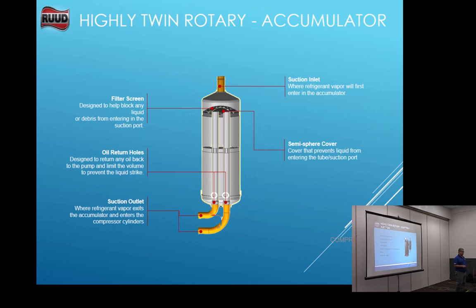So this is our suction line that comes in right here. Should we get any liquid coming back into here? If we got liquid coming back into there, we could have what? A dirty coil, a bad TXV, bad airflow. We're not getting the superheat across that coil when that liquid goes into there. It means it's not all flashing off into a gas, right? And we're getting liquid droplets coming back into that suction line, okay? If we do that, this is here to help. It has a screen in here where the droplets hit the screen, come down to the outside, and we've got this little hole down here.